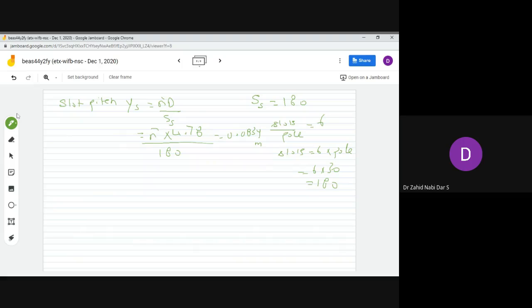One more thing, last time I also told you about the formula for net iron length. All the material will not be required, as some 90% of the material is used and some is wasted. So the net iron length required, Li, is equal to Ki into the total length which you calculated, minus the ventilating ducts NV times the width of each duct BV.